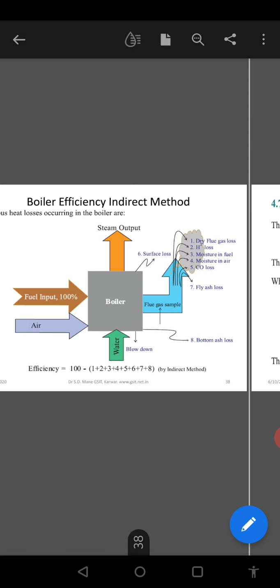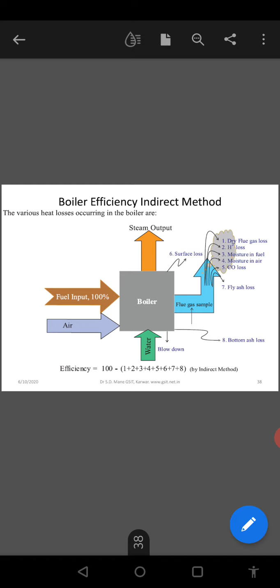But in practice, because people don't have knowledge, they tend to give more air. Please understand, though air is free, this extra air carries the heat, and we are not interested in sending heat out through flue gases because we have paid for the fuel. So we always closely monitor the oxygen level in the flue gases as well as carbon monoxide. Carbon monoxide tells you about the combustion levels. If carbon monoxide is present, it means the combustion efficiency is low. And if more oxygen is present in the flue gases, it means we are supplying unnecessarily excess air, and that excess air is carrying away heat. These are not desirable from a boiler or furnace point of view. Please note this.